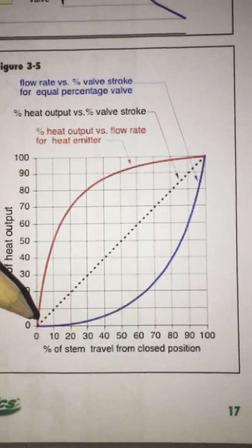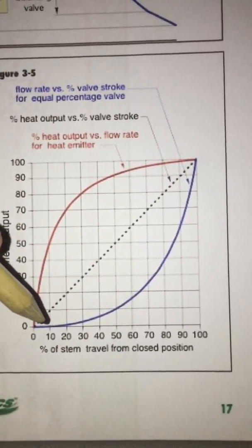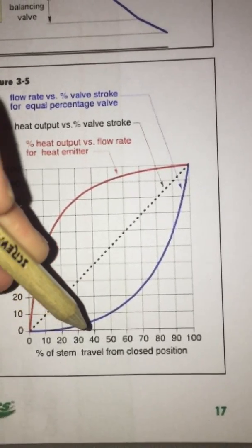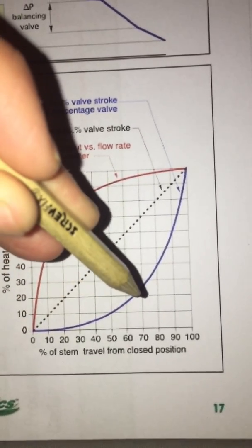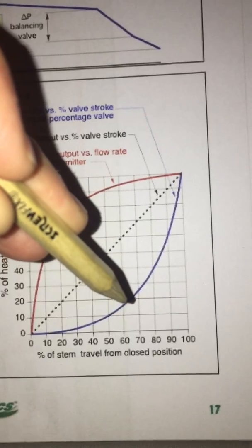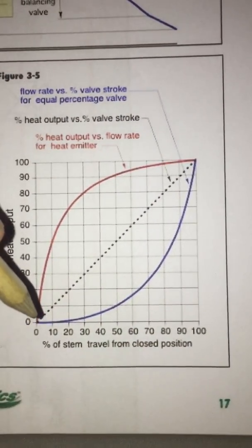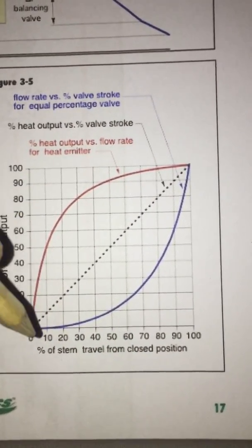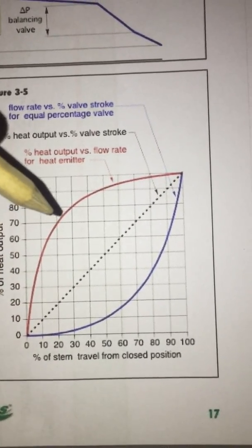So you can see on the high authority valve, when we open the valve we get a nice gradual increase in flow, more proportional to the valve opening. On the low authority valve here, we crack the valve open a small amount, we get a sharp increase in flow.